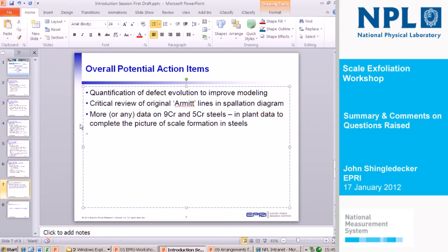So John, I think about design as well, of the boilers, and I think particularly about two items, and both of them came up today. One is that Paul and I have known each other long enough to know that there's something in what we're saying here that there might possibly be a difference. The boilers in the CEGB were designed by their own design department, and they might have different temperature limits for these different materials that actually control the oxidation properties and therefore the exfoliation. So I think it's worth looking at this plant data.